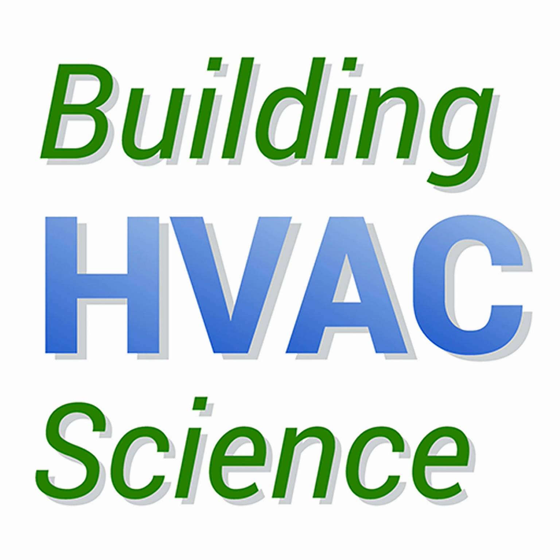So now we've got the supply side and the return side temperature, which means we can tell your vent-to-vent delta T, or performance. And we've also got insights into airflow coming from static pressure. That's super powerful—understanding static pressure can tell you dynamics around face velocity across your filter and total airflow of the system versus what it was designed to do.